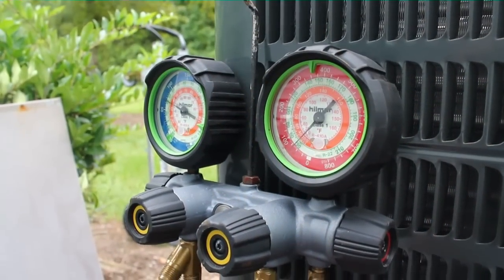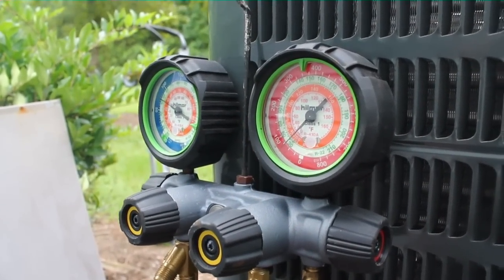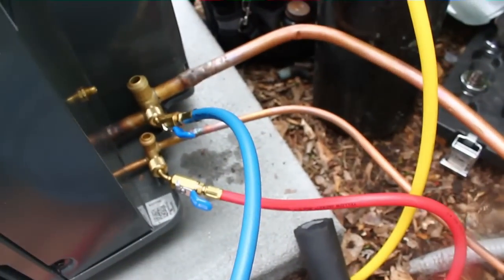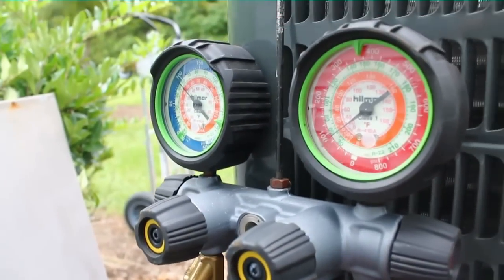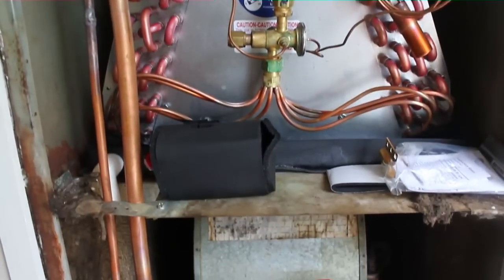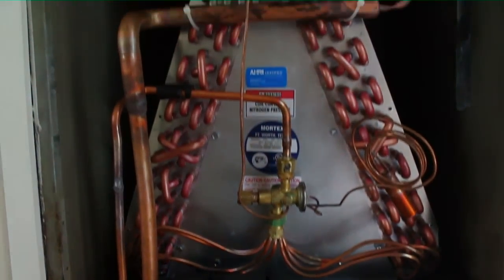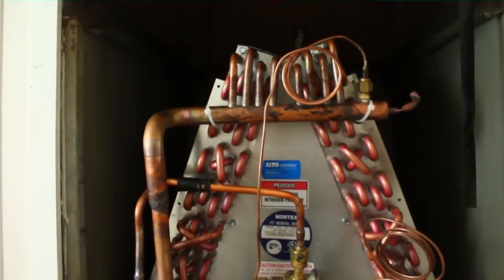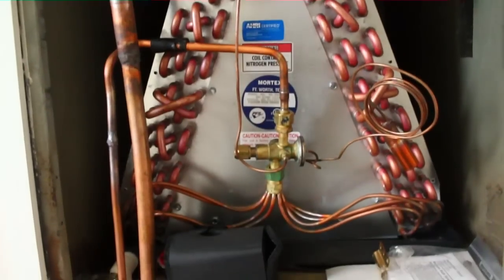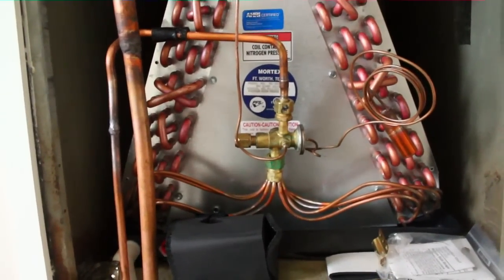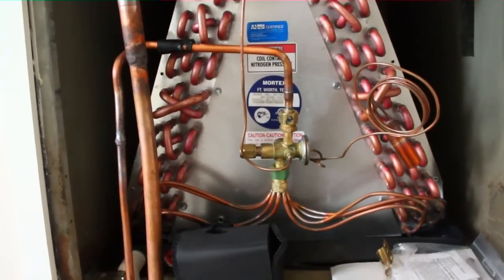I am now putting nitrogen on the rest of the system, hooking the Hilmor gauges here up to our line set. We will put about 50 to 100 pounds on it to start with, see if there's any major leaks, and then move on. We're at the furnace now and the coil, just making sure I don't hear any leaks. It appears we are just fine as far as audible noise. I'll go ahead and finish this up as far as pressure testing, and then I can finish trimming out this TXV, hooking up the bulb.